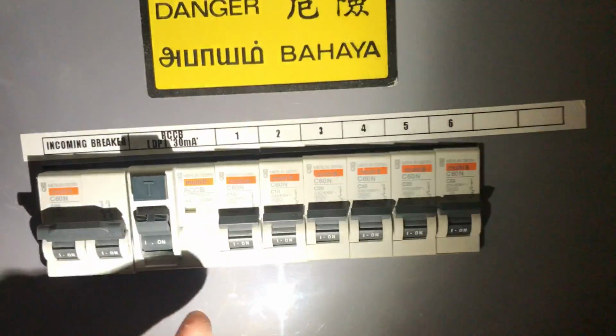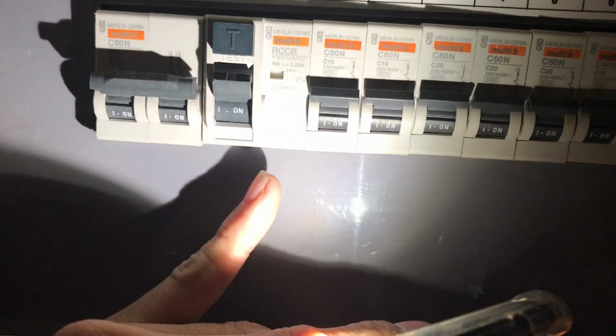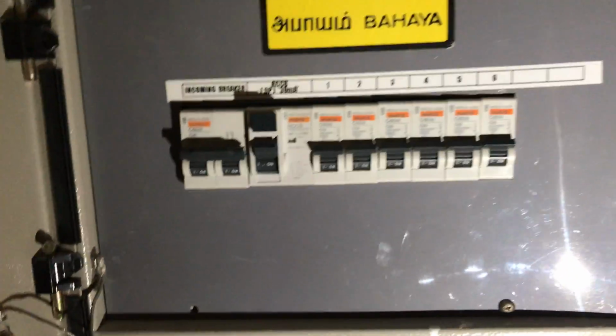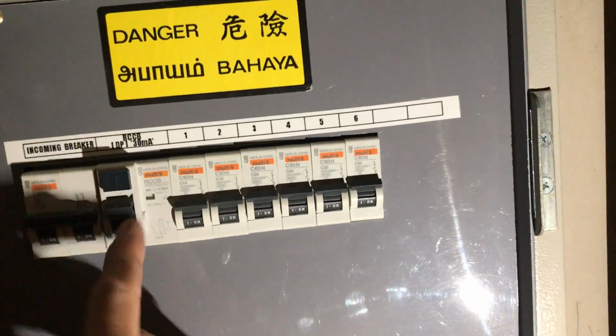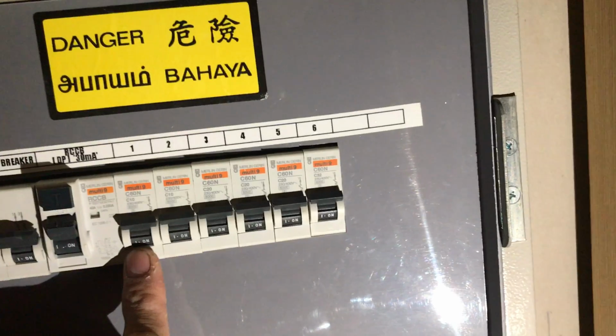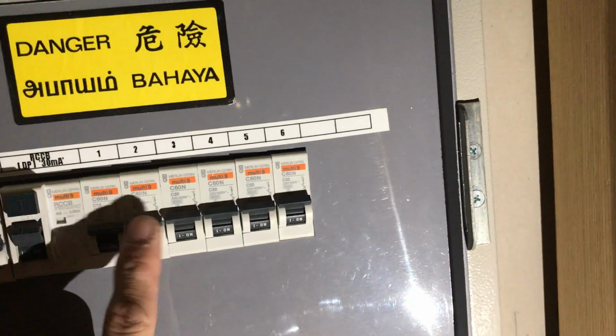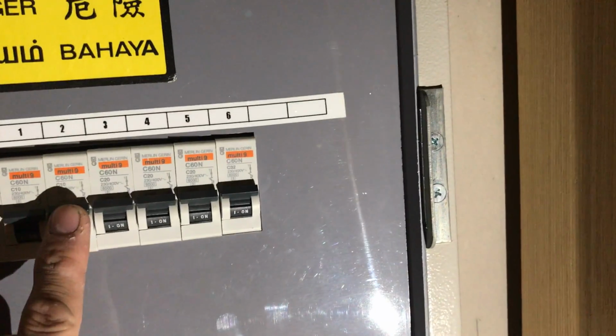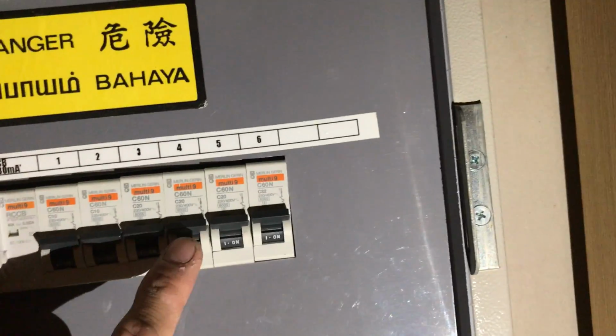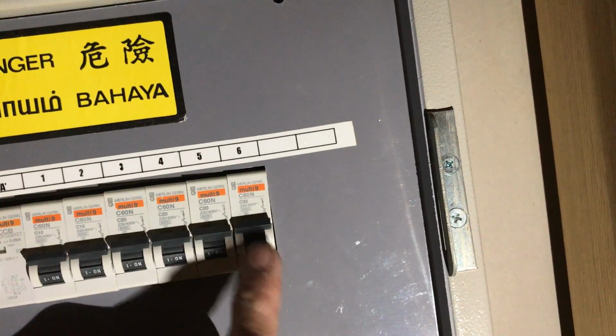40 amps, and the RCCB is 40 amps. This is the RCCB, not the RCBO, so it doesn't protect against short circuit, it will just trip if you touch a live wire. These are all the standard MCBs: 10 amps, 10 amps, 20 amps, 20 amps, 20 amps, 32 amps.